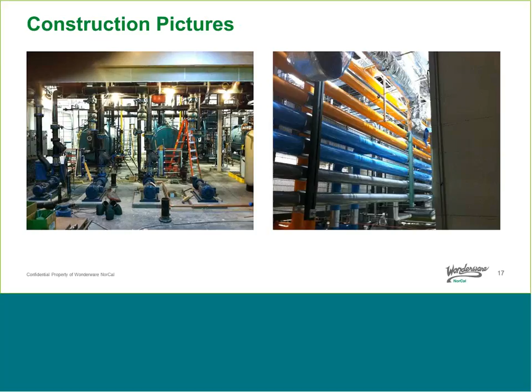So now we'll get into the validated system. So this was referenced as the process automation system, or PAS. So this is the CGMP system. And again, there's 2 PLCs that really govern this, one dedicated to environmental monitoring and one dedicated to the WFI, or water for injection system. There's 4 remote I/O panels. And this system integrated both Ethernet and Modbus protocols, and it went out to 44 pieces of the process equipment.